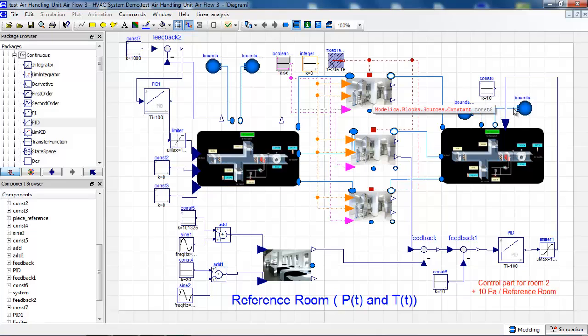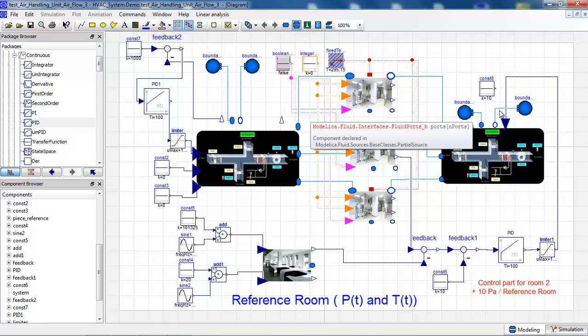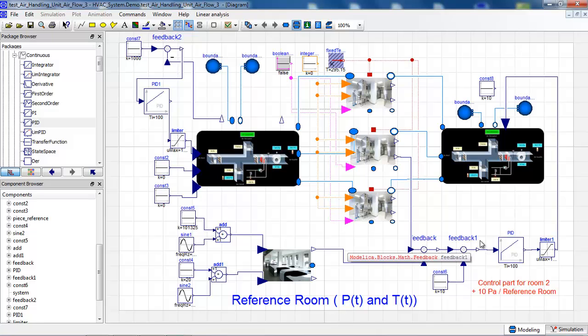through a limiter. I will do the same for the absorption part, and there I want to control the pressure inside my room number 2, and also the pressure inside room number 1 and room number 3, because we saw before that the relative pressures between room 1, room 2 and room 3 are constant. To do so, I will use a PID here, and I want to control the pressure in room 2 to be plus 10 Pascal compared to the reference room, which is here.